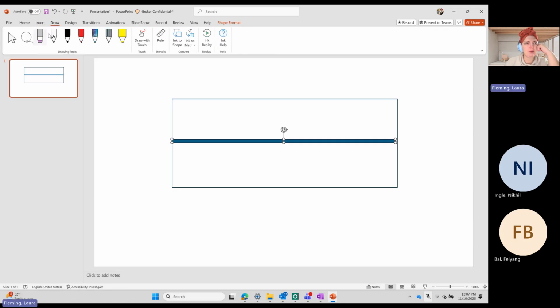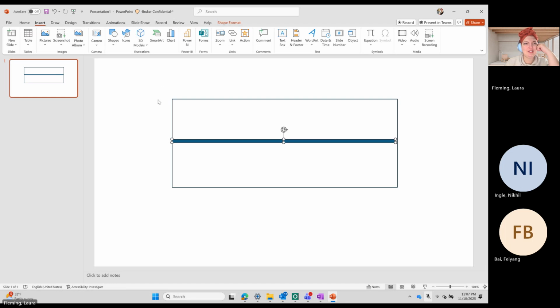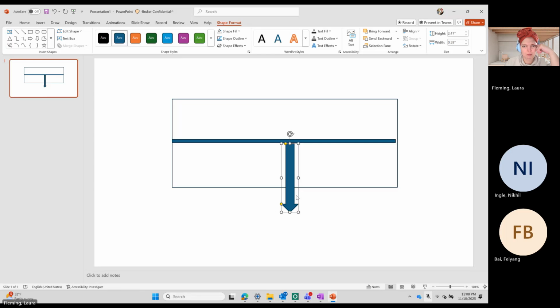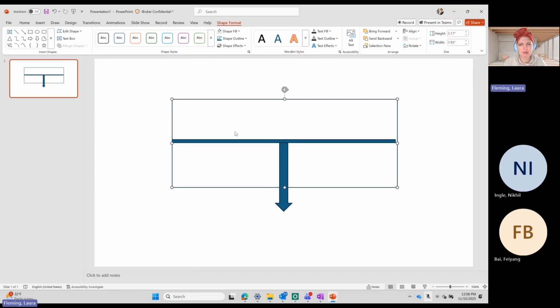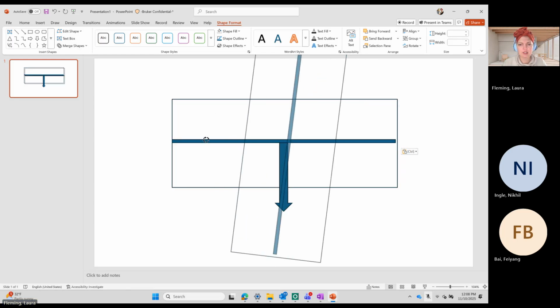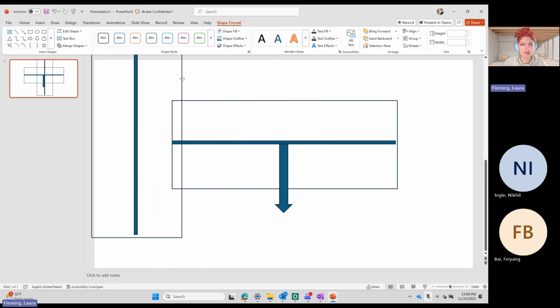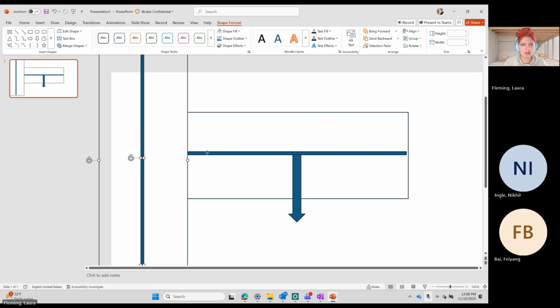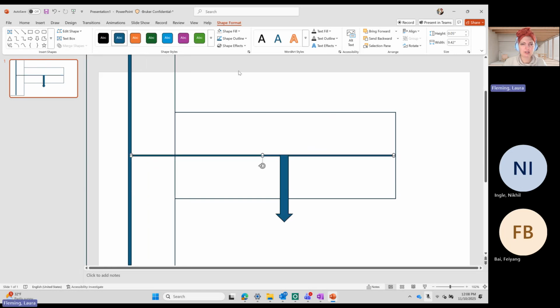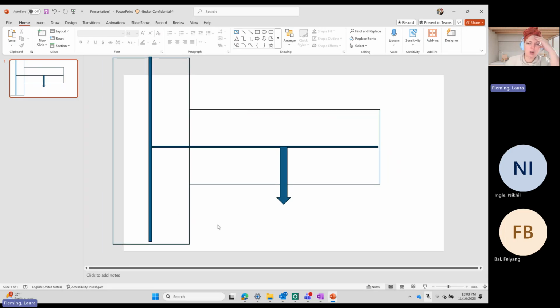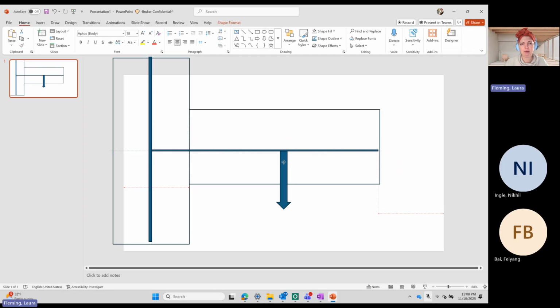All right. So here is a rough image of what the transducer looks like. Right, we got our probe and our center plate. Hopefully this is making some sort of sense. I wanted to talk about what goes on in the lateral transducer. Okay, so there are two of these lateral transducers on either side of the transducer. Now, if you recall during the normal force training, what we talked about was that physically we can only apply a voltage to this bottom plate. So we can only pull this probe and this center plate down. We can't push it up. However, due to physical restraints on how this is built, we can actually control from either plate. The problem is we only calibrate to one, so we need to pick one.